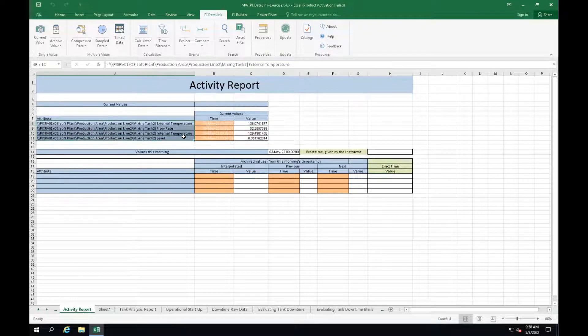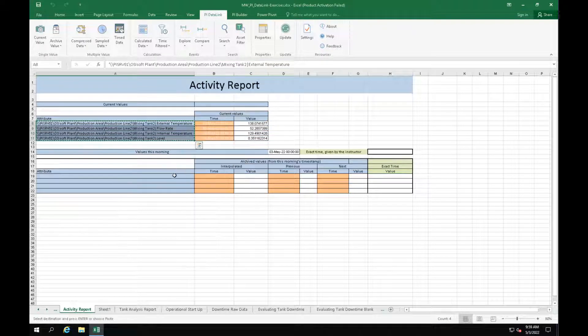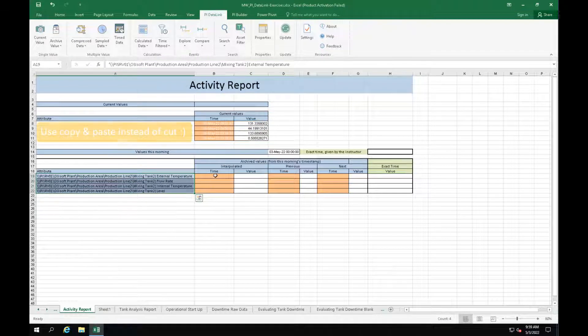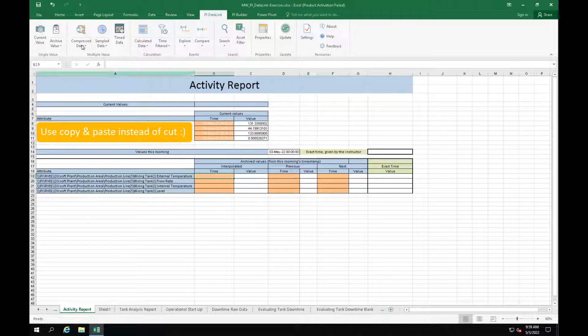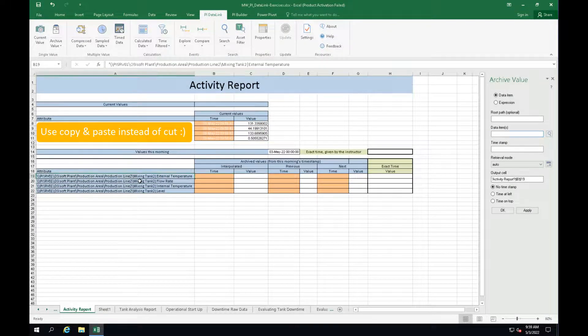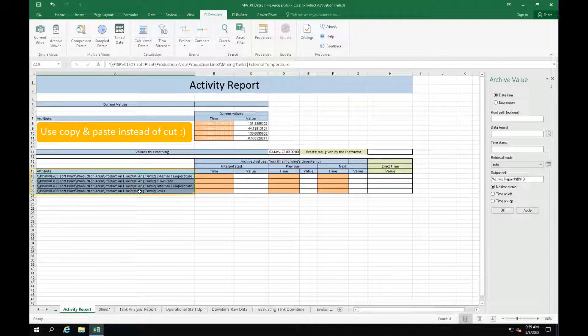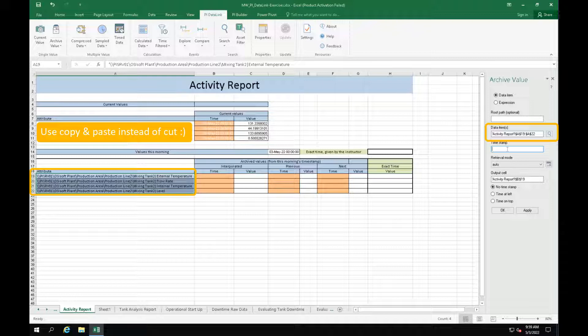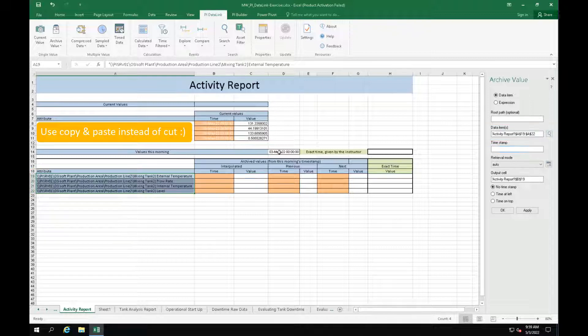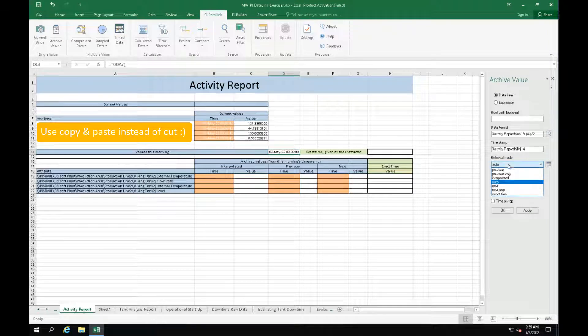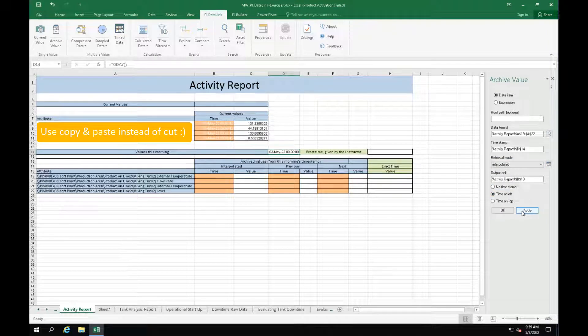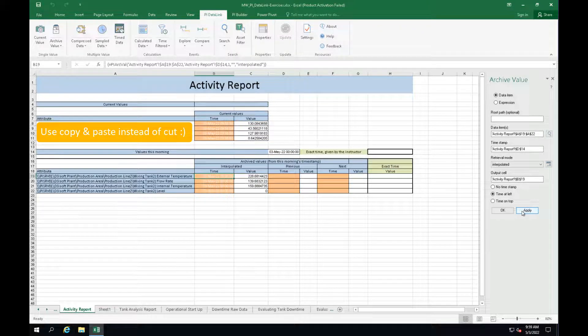So first let's copy and paste the attribute names. Now click on cell B19, select the archive value function. Now select the attributes as our data items. Remember that we can select all of them in a single step. Select cell D14 as timestamp, retrieval mode interpolated and time at left option for the timestamp. We will repeat it twice but now choosing the previous and next retrieval modes.